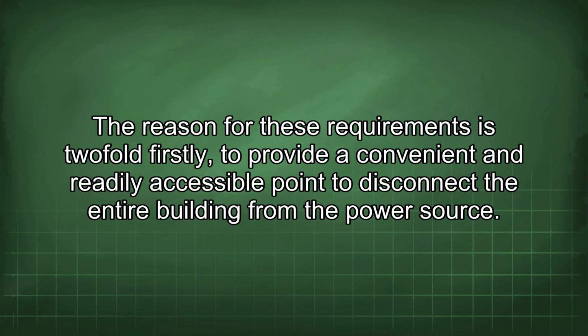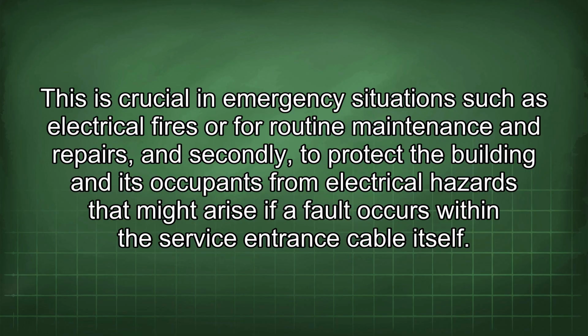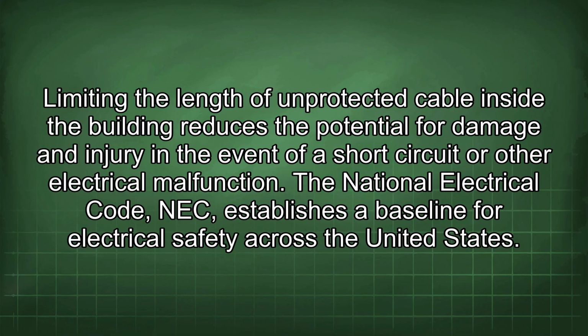The reason for these requirements is twofold. Firstly, to provide a convenient and readily accessible point to disconnect the entire building from the power source. This is crucial in emergency situations such as electrical fires or for routine maintenance and repairs. And secondly, to protect the building and its occupants from electrical hazards that might arise if a fault occurs within the service entrance cable itself. Limiting the length of unprotected cable inside the building reduces the potential for damage and injury in the event of a short circuit or other electrical malfunction.